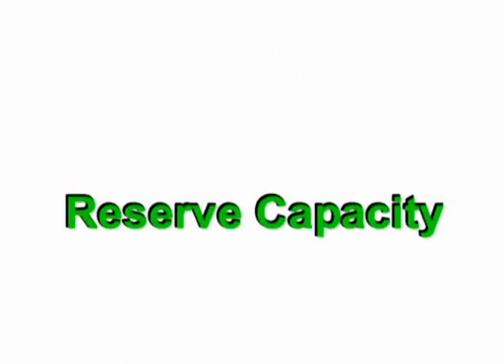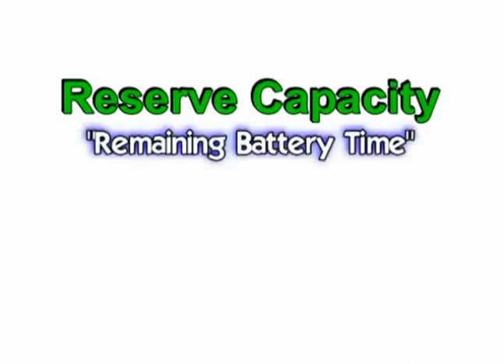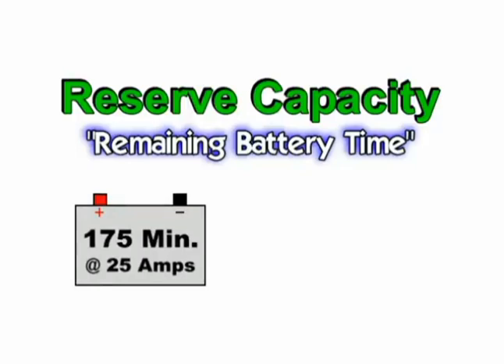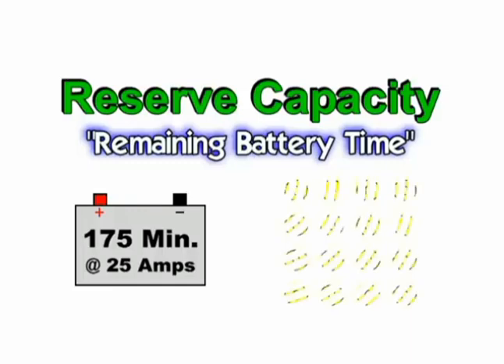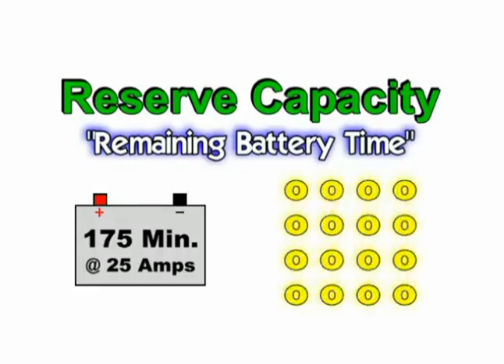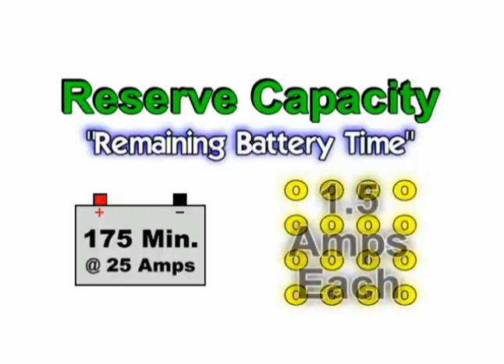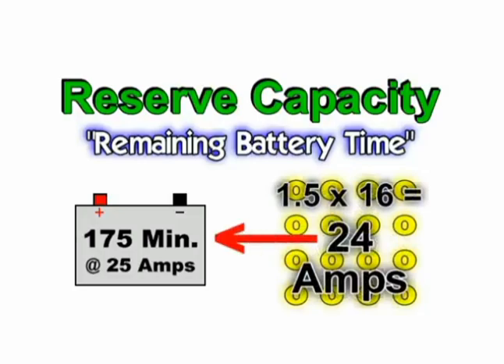Reserve capacity is how we rate or guess the time a battery will last. Let's say you have a 12-volt battery with a reserve capacity of 175 minutes. In theory, the battery will last 175 minutes at a 25 amp draw. Now if, not likely, you had 16 lights lit at the same time, each drawing 1.5 amps, your battery would be dead in 175 minutes.